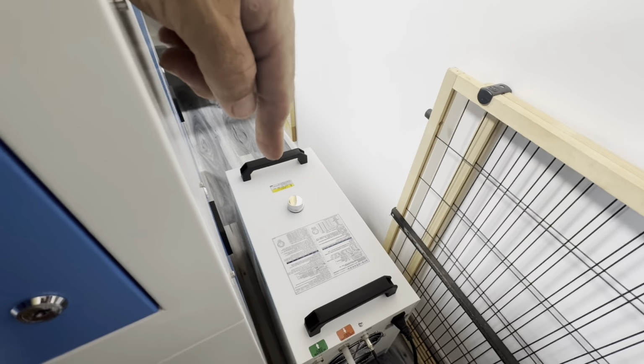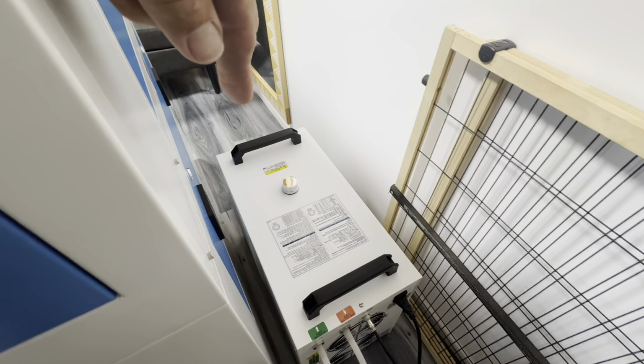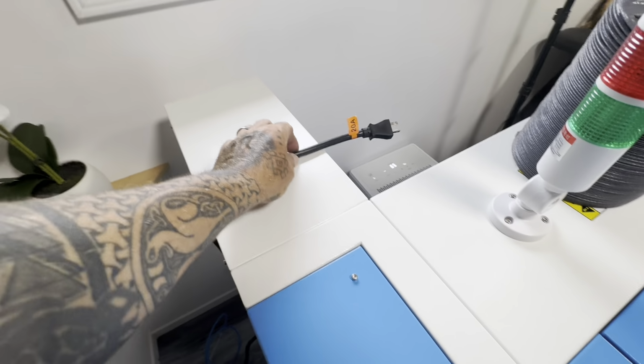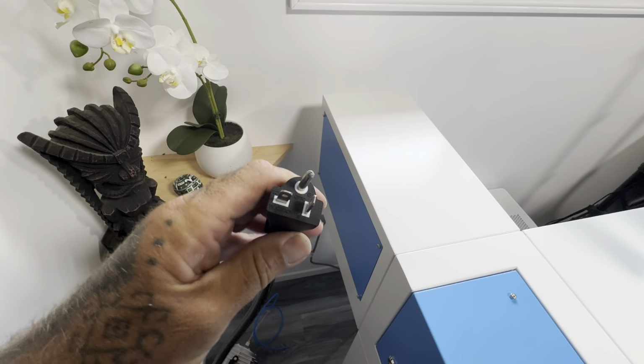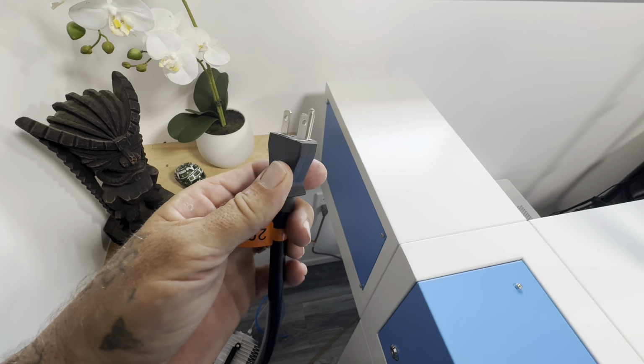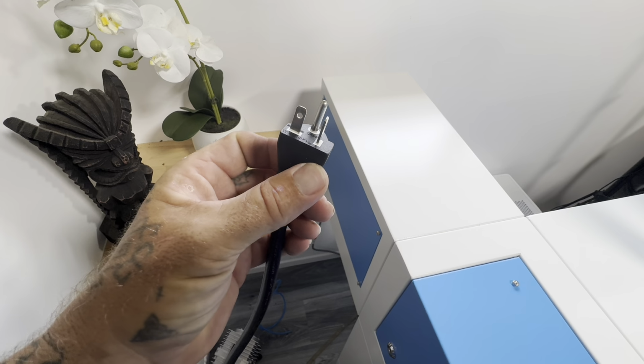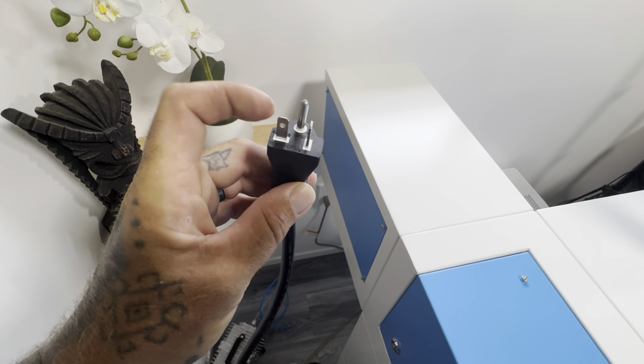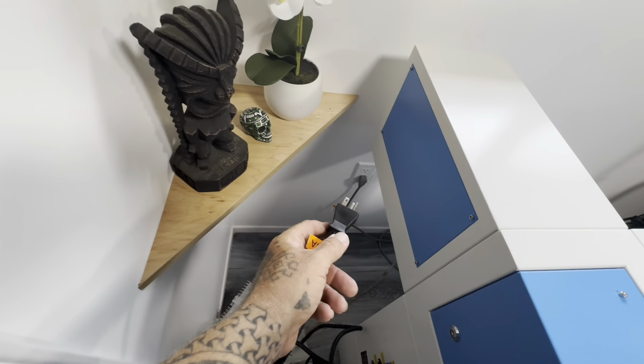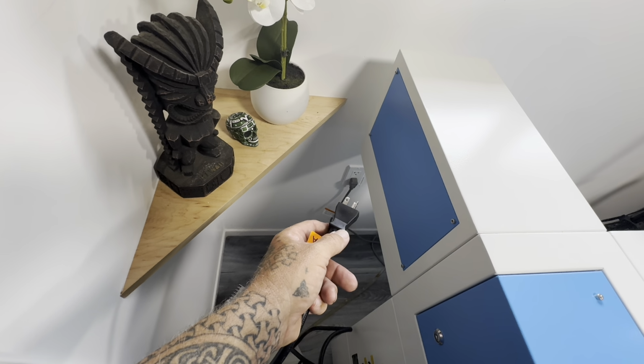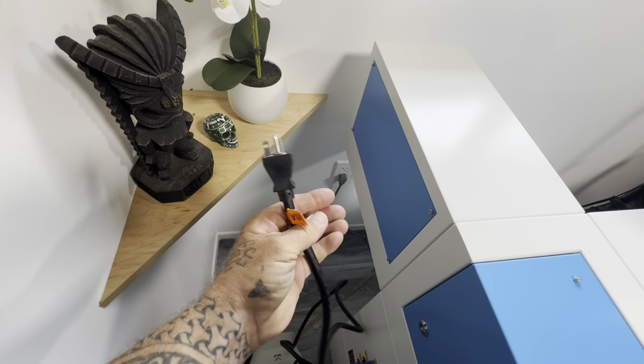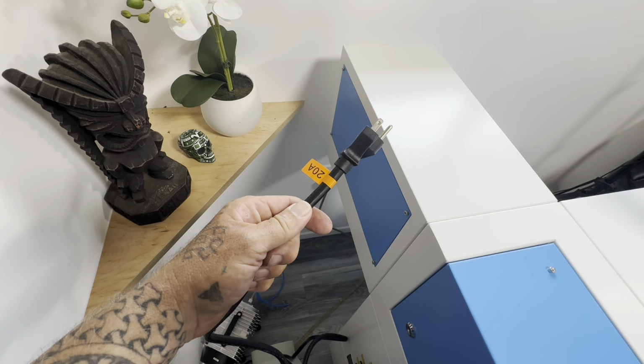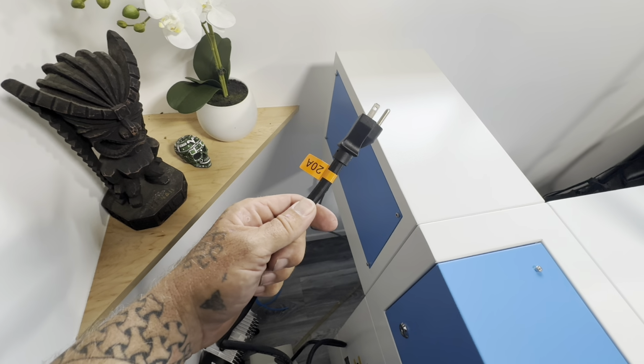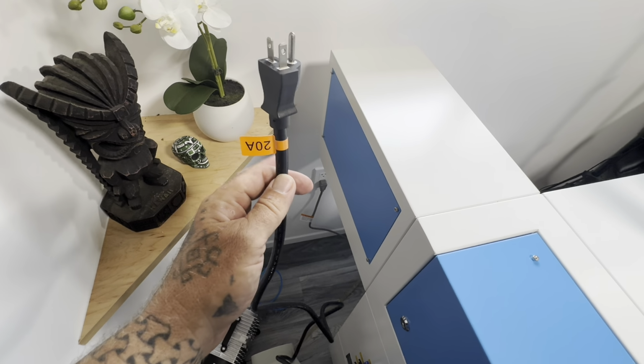I need to go to the store and get some distilled water. So it takes about 2 gallons of distilled water to fill the chiller. And one thing I just noticed is this is a 20 amp plug. Even though this is regular 110, it requires a 20 amp plug, which is why this is sideways. So I cannot plug it in to here. So that's going to be an issue. So now I'm going to have to run either a dedicated line, which I was thinking about doing anyways, just so that it's not connected to anything else.